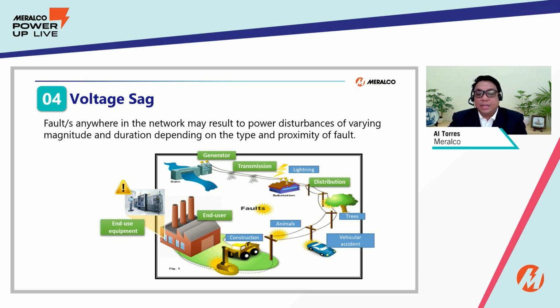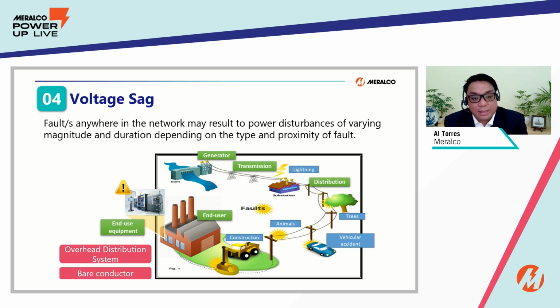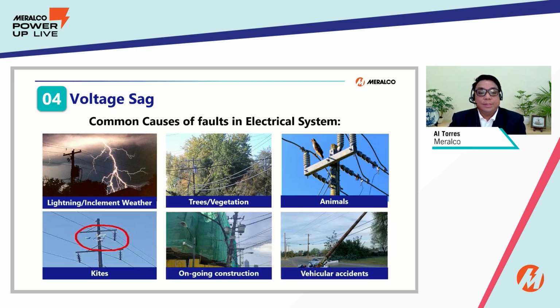Let me illustrate the voltage sag problem. I have here the power supply chain, from generation, transmission, down to the end-use equipment. Given the overhead nature of our electrical system and our lines being bare conductor, any fault in the network may result in power disturbances of varying magnitude and duration, depending on the type and proximity of the fault. So these are the common causes of voltage sag in the electrical system.